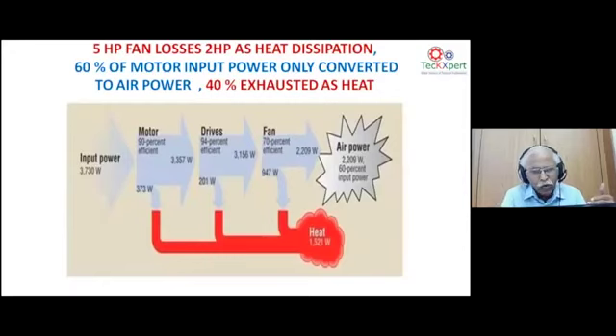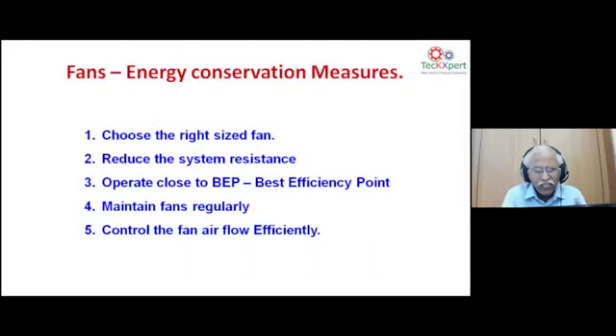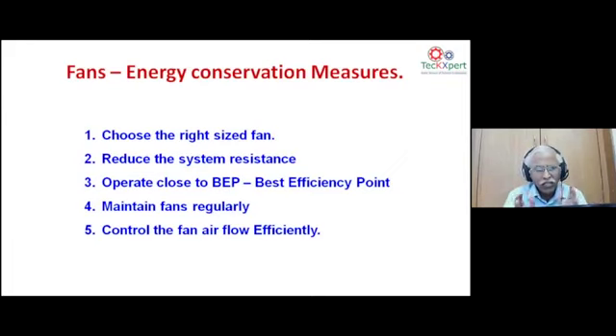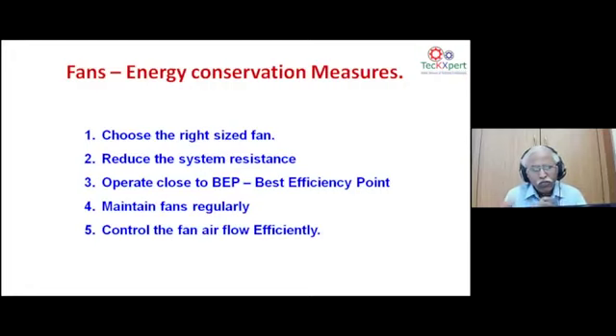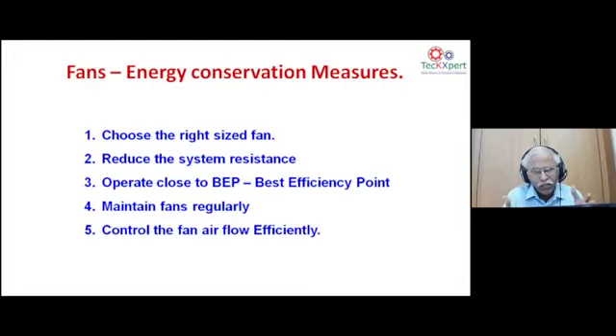Small drops of efficiency, when improved upon, automatically improve the overall system efficiency. There are five macro dimensions for energy conservation in blowers: right-sizing the demand, optimizing system resistance, operating at the best efficiency point on the fan performance curve, maintaining fans regularly, and controlling fan airflow efficiently.